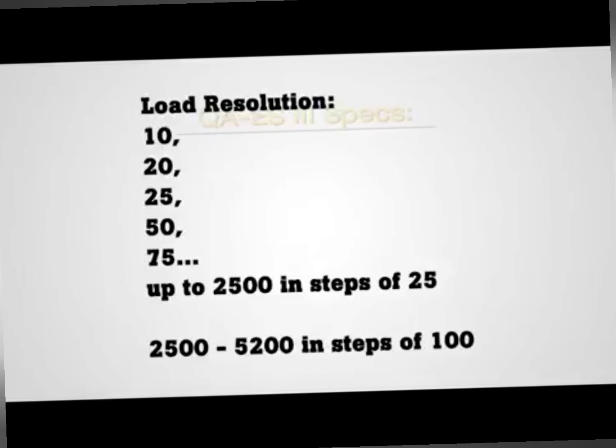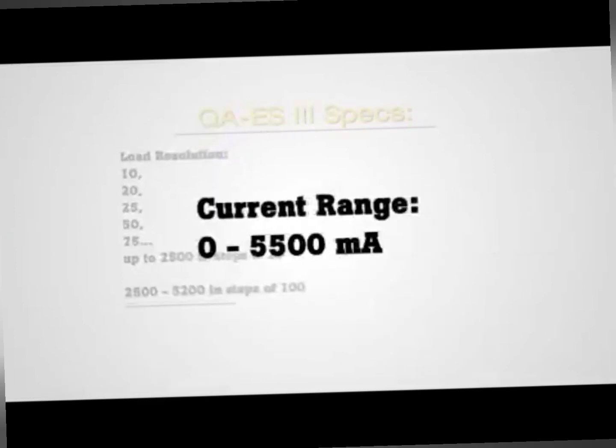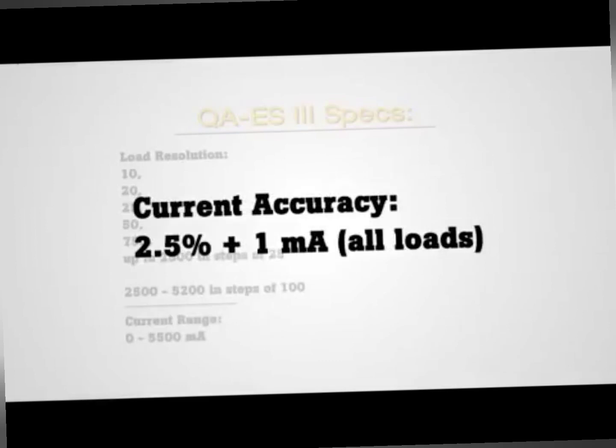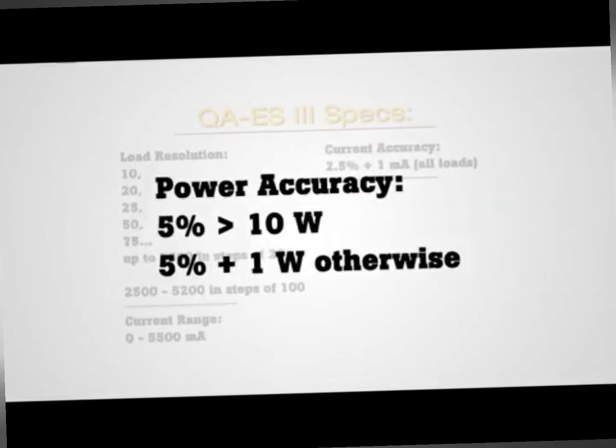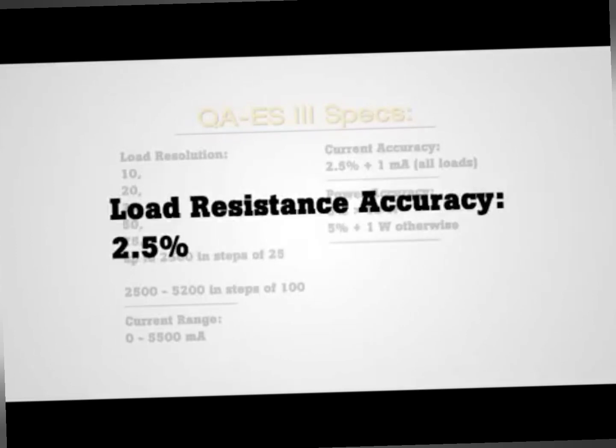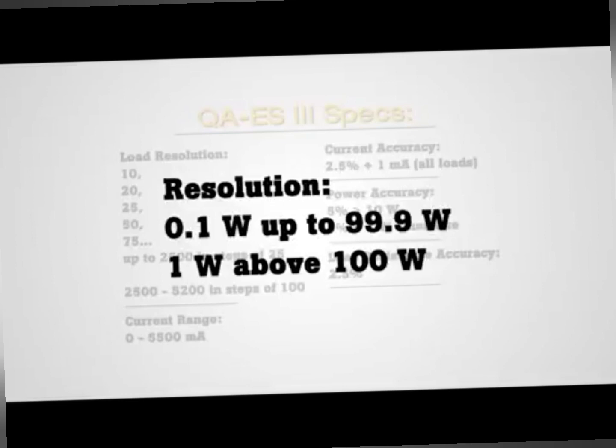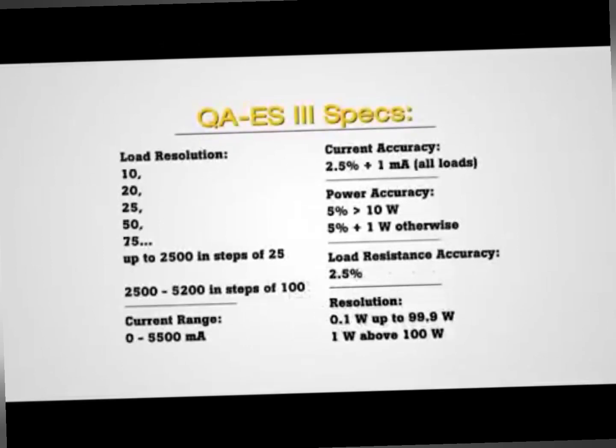Notably, the QA-ES3 has a 20-ohm load to support Valley Lab electrosurgical units, including the Force Triad. The QA-ES3 also has double the RMS current range of its predecessor. It can measure current from 0 to 5,500 milliamps. Plus, it's twice as accurate with current accuracy of 2.5% of reading plus 1 milliamp for all loads. It's exceptionally accurate with generator output power accuracy of 5% greater than 10 watts and 5% plus 1 watt otherwise. In addition, it provides a load resistance accuracy of 2.5%. The QA-ES3 is also highly precise with a tenth of a watt resolution up to 99.9 watts and 1 watt above 100 watts for power measurement.